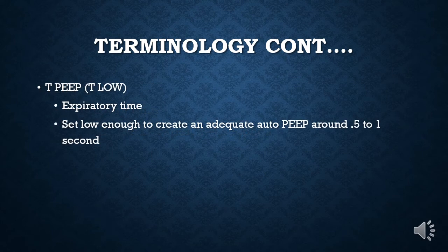And last but certainly not least is the T-peep or the T-low. Again, T standing for time. This is actually one of the most important settings that exist in this mode of ventilation. It's the time that you're going to be spending at that low pressure or PEEP, which of course, if we set it at 0, it's the time we're going to be at 0. Now, the reason why this gets very important, if we're not setting PEEP, then we need to create some form of auto PEEP with our patient. We'll be getting to that more later in the next video. So to have a proper auto PEEP, you usually have to have this T-peep or expiratory time very low. Typically 0.5 to 1 second, but we'll get into that a little bit more as we go along in these videos.